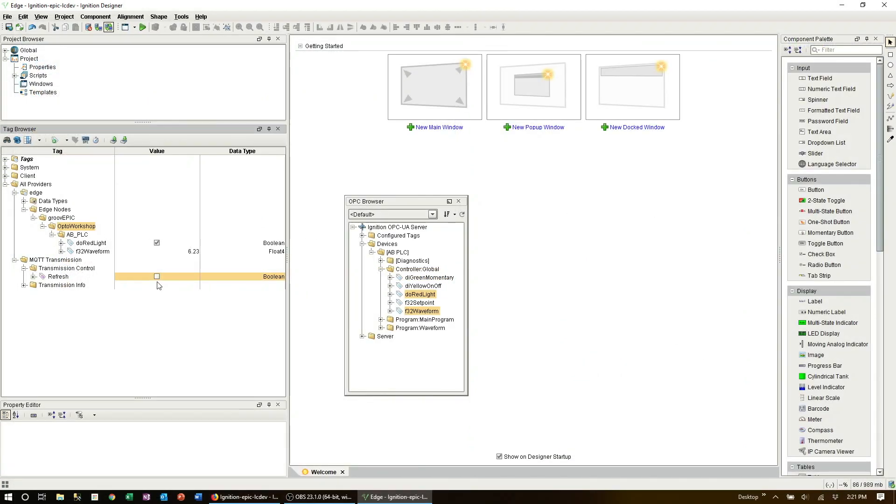Now because this is MQTT with Sparkplug data will be published only on change, otherwise known as report by exception. Now this saves a lot of communications overhead.